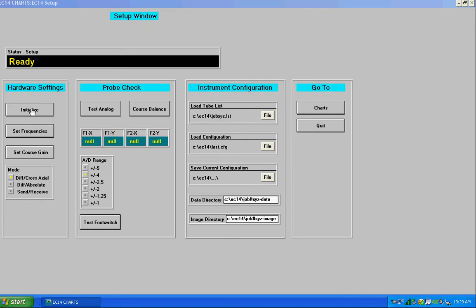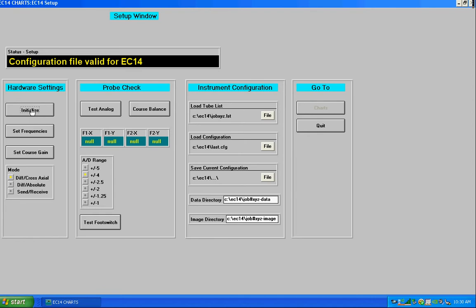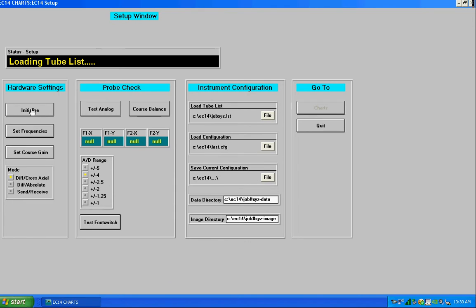Initialize actually runs when you start the program, but I'm going to go ahead and click on the initialize button and what it's going to do is configure various instrument settings based on the last.config file. That last.config file is a file that was saved the last time the program exited and it configures the instrument and also reads in a tube list if it's available, loads the user's color preferences, things like that.